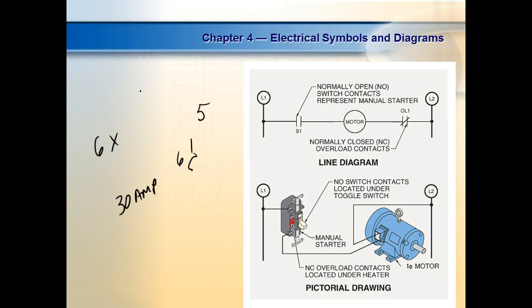So what we do though on your bigger motors, and also in your dual voltage motors, where you can wire it for a high voltage, which means it takes less current to run that motor, or you can wire it for a lower voltage and higher current. Then the overloads are built outside, and we have the ability to set it up for low current or high current, right? If they're internal, then we usually don't draw it as part of the circuit, but here's the overload right there. So that switch, and notice the current of the motor runs through the overload.